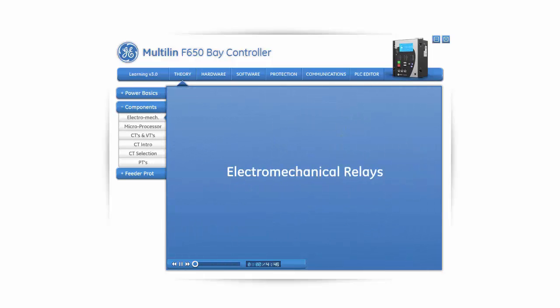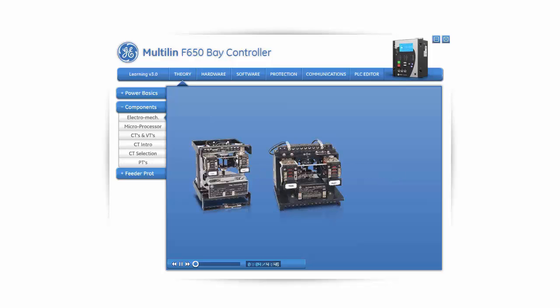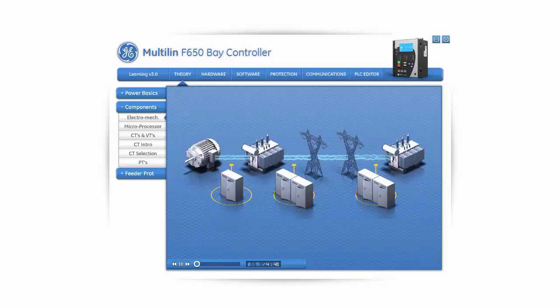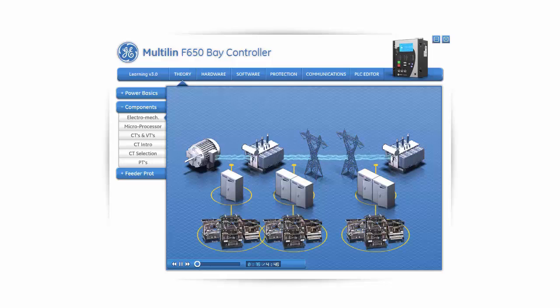Until the early 80s, almost all protective relays in use were based on an electromechanical principle of operation. Their designs were limited in configuration, and most supported only one protective element, resulting in a requirement for many expensive electromechanical relays for a protective solution. This, coupled with the expense of periodic calibration, translated into high initial cost for an electromechanical relaying solution, in addition to high maintenance costs associated with the mandatory periodic calibration of each electromechanical relay within the system.